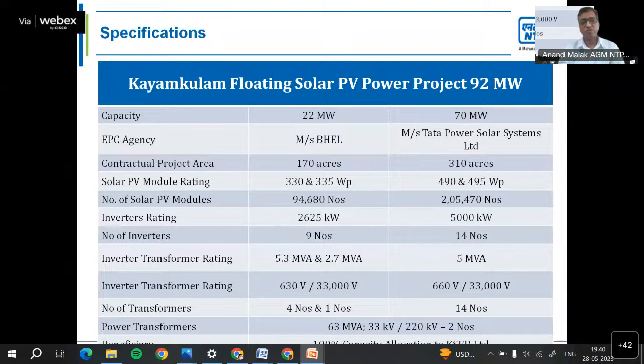In 22 megawatt, we have 330 and 335 watt peak modules from Vikram Solar. In 70 megawatt, we have 490 watt peak modules. They are bifacial solar PV modules with half cut cells. The number of modules in 22 megawatt is around 94,680, which comes to around 31.5 megawatt DC input. In 70 megawatt, it is more than 2,05,000 modules, which comes to around 101 or 101.5 megawatt.